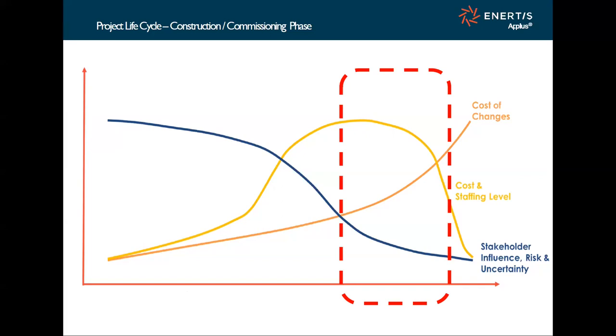Ideally commissioning goes smooth as butter and nothing ever goes wrong, but if you've experienced that in real life, that's not true—things happen. How you respond to it, by having equipment properly labeled, really cuts down on de-risking delays on your project. And it's not just that—it's a safety issue too. When doing lockout-tagout on equipment, especially commissioning projects on a feeder-by-feeder level, having equipment labeled protects everyone.